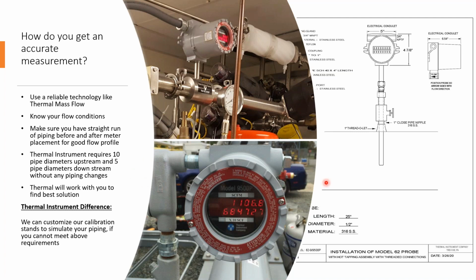Something else just to point out, when we send you a quotation, I put just a snippet of a drawing here, but this shows one of the different process connections that's available to you. This would be our hot tap, and this is just on our insertion probe. What this hot tap allows you to do is, if your process is running and you need to remove the unit for any reason, you can pull the unit up through the port, close the valve off, and keep your process running.